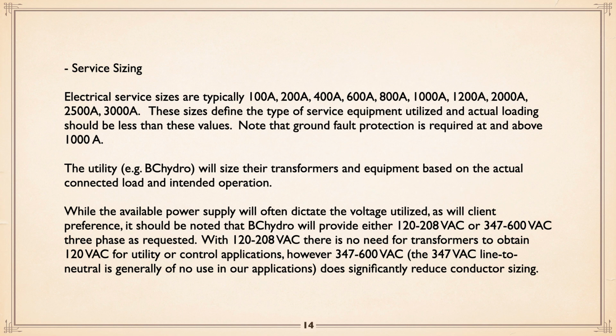While the available power supply will often dictate the voltage utilized, so will client preference, it should be noted. Now I'm talking about BC Hydro, as I mentioned, either 120/208 or 347/600. 120/208 is nice because you don't need any transformers to obtain 120 volt for utility or control. With 347/600, the 347 line to neutral in pump stations, treatment plants, whatever, is effectively of no use whatsoever. And the higher the voltage, the smaller the conductors.